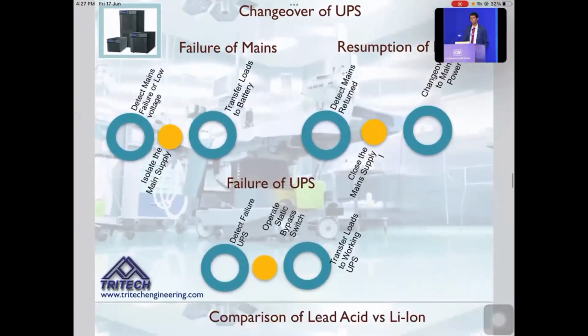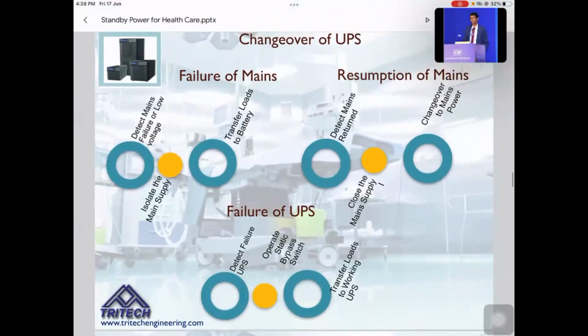Again, how the changeover of the UPS happens is what is explained here. In the case of a mains failure, it will isolate the supply and transfer loads to the battery. And similarly, when the main power resumes, the main supply is closed, and the control goes back to the mains. In the case of a failure, what happens is that the static bypass switch operates, which takes something like 4 to 5 milliseconds, so you may not even be able to notice it. It will not basically affect the loads that are being fed by the system. So we have these three scenarios: one is the failure of the mains, another is the resumption of the mains, and the failure of a UPS, which is handled by different systems within the UPS. So this is one of the basic block components inside the UPS.